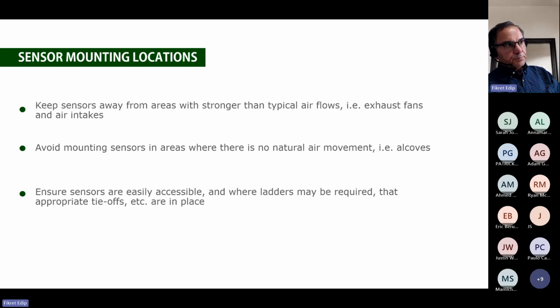The location is important. Keep sensors away from areas with stronger airflow. I have seen a lot of times, especially in Ontario, I was called to a city facility where they repair trucks. They mounted the sensor near the overhead gate. Each time the gate opens and closes, especially in winter, the air rushes in and puts the system into alarm. So it's very important where you mount your sensor, avoiding areas where there's no natural air movement. As I said a few minutes ago, the only way the gas gets from the high concentration area to the low is by diffusion. So you don't want to obstruct that.